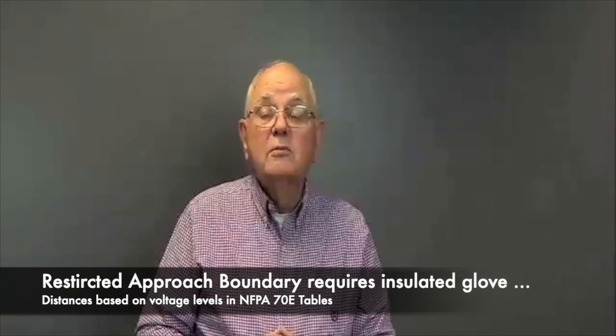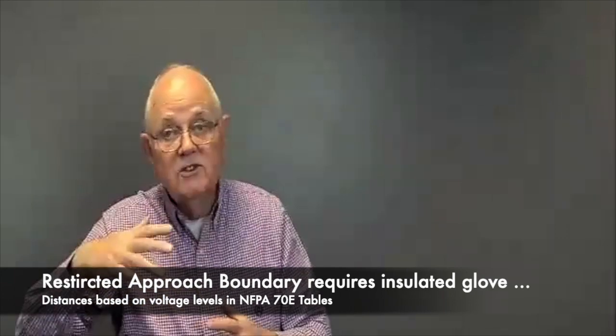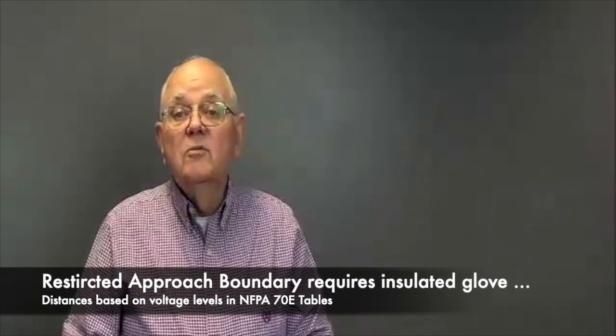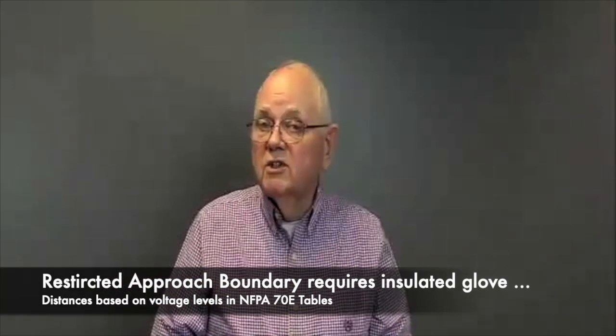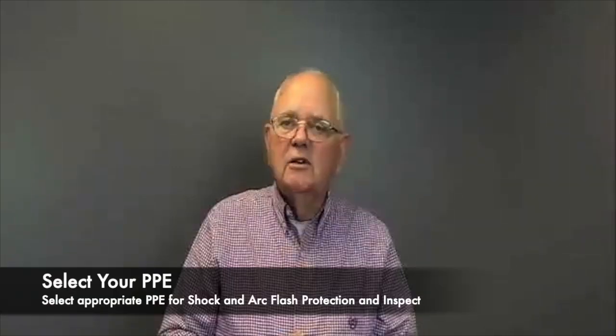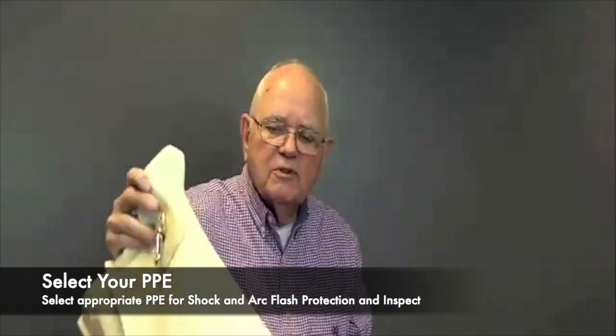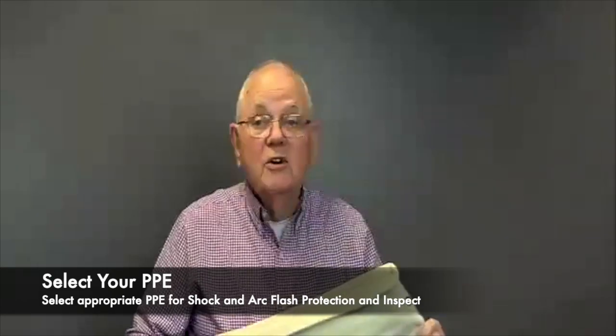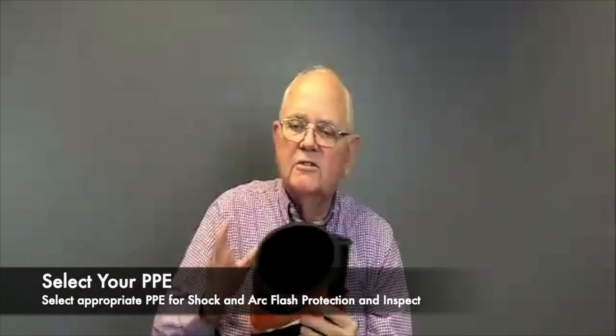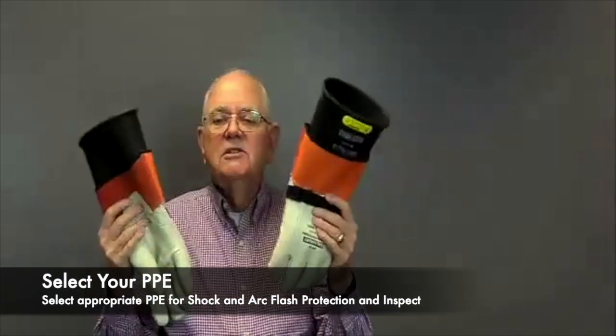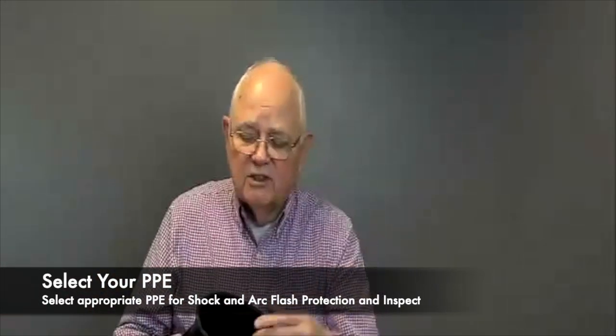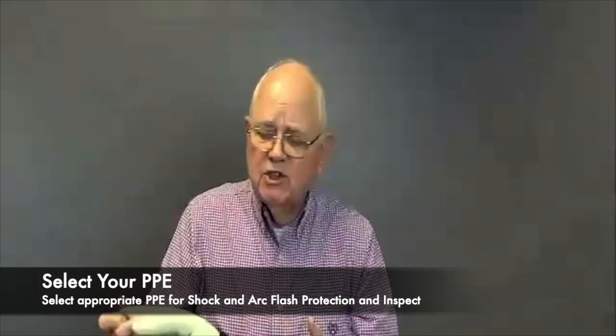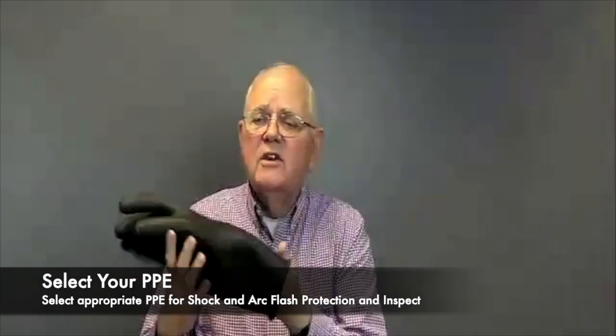The second boundary area is the restricted approach boundary. The restricted approach boundary for all of our medium voltage levels, anything from say 1,000 volts on up to 15 kV, is going to be 2 feet, 2 inches. Anything I take within 2 feet, 2 inches has to be insulated. So let's talk about some of these things. First of all, for shock protection, one of the basics is rubber goods, right? And we think of the basics as our rubber gloves. And these rubber gloves are larger than what you may typically use, a little bit thicker rubber. So if you're using class 0 or 00 gloves, class 0 up to 1,000 volts, these class 2 rubber gloves will protect us all the way up to 17,000 volts.